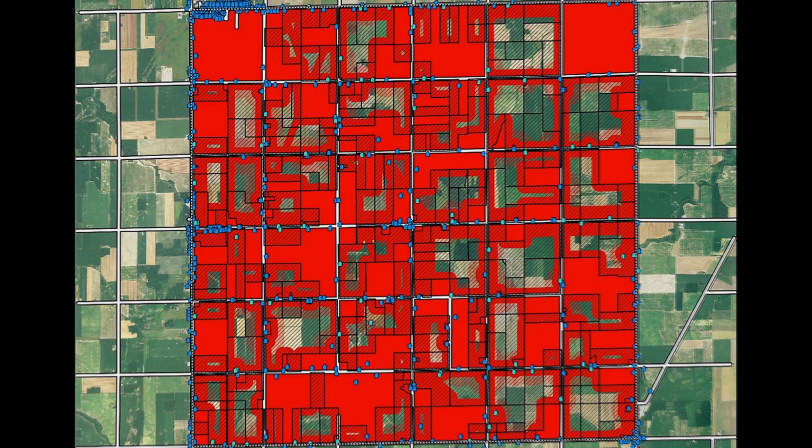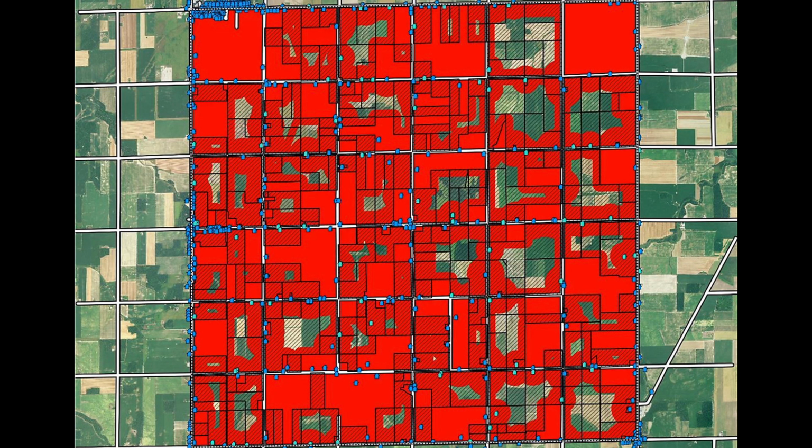And the last one I'm showing here is what I call occupied structures, but it's mostly homes. But we also include churches, we include schools. If we had places of business, offices, we would also include offices. So we include those, and that has a minimum setback usually of about 1,000 feet, just absolute minimum. And then we usually apply closer to a 1/4 mile for most of those buildings as our preferred. And where we can, we go higher. And where it makes sense, we go higher. Because those are our areas of most concern. That's where people live, right? So we want to really take that into consideration.